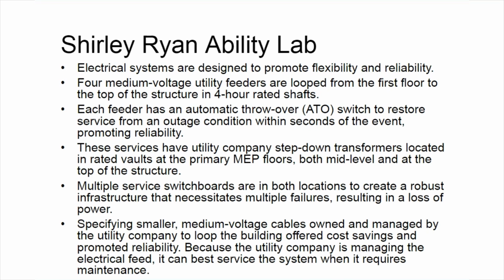So what we did was we approached the electrical system where we've got 4 utility feeds coming in that are looped from the first floor all the way up to the top of the building in 4-hour rated shafts. They're all connected with an automatic throwover switch from the utility side so that we're restored within seconds of an outage. And then in addition to that, we've got multiple utility step-down transformers located in vaults on the primary MEP floors, both mid-level and at the top of the structure, that take that down to utilization voltages.